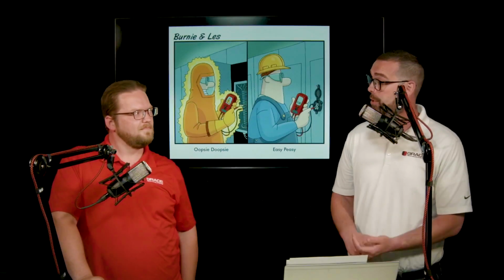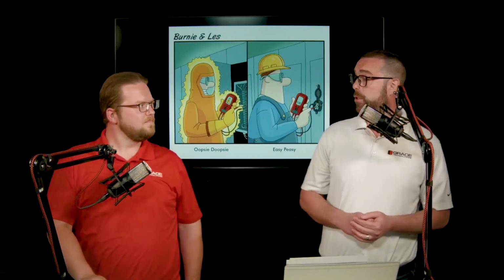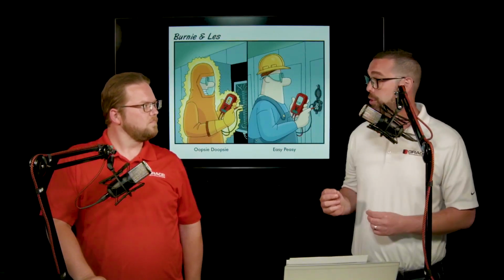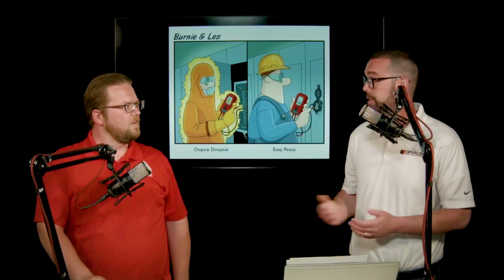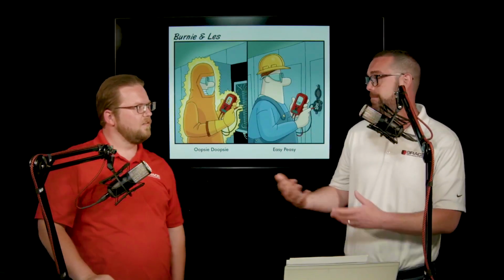That's a great question. So the device, as I mentioned before, will be UL listed. On top of that, it's also going to carry an IP2X rating because of the built-in current limiting resistors. So on our standard safe test point device, that is 102 kilo ohms. On the check volt, it's 164. That is how we're able to get that IP2X finger and touch safe rating. Now, with that built-in impedance, it's actually limiting the current to milliamps. So that exposure, and in accordance to OSHA document 3075, page number 7, any shock hazard under 6 milliamps is considered a slight shock. So bearing that in mind, there is no risk of bodily harm that could potentially be caused because it's limiting. Yeah, there's no injury risk there as well.